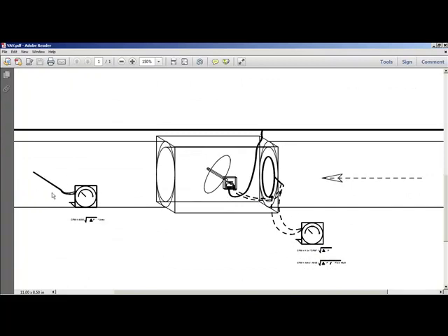flow of the box. The outlet flow is going to be, our CFM is equal to 4005 times the square root of the velocity pressure times the area. It doesn't have to take into account the multiplier. So this way we can compare our reading to the output of the box, and we should get the same.